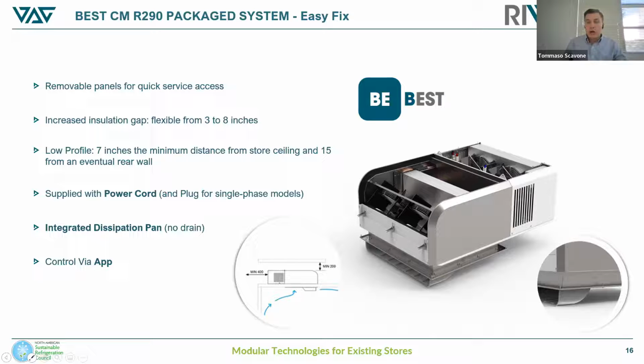All units are supplied with power cord, and the single phase version is also with the plug. Another huge benefit of this product is maximizing the storage space, thanks to the deflector inside the room that is less than 5 inches high, as you can see. In fact, the evaporator is outside of the walk-in, and that doesn't take out any space at all from the walk-in itself. So you can increase the storage space, adding more shelves compared to having a cubic evaporator inside the walk-in.